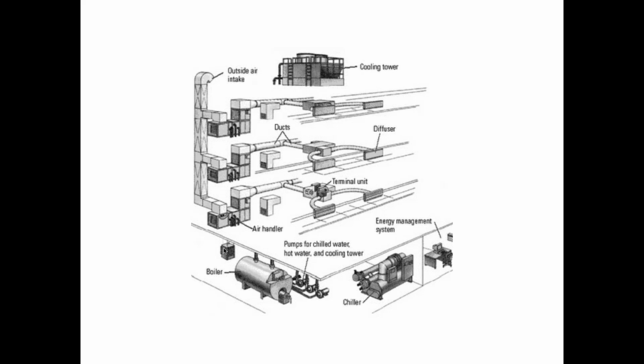So it's a problem. Instead of putting a Freon coil for cooling in each one of these air handlers, let's put a machine in the basement, which has an evaporative coil and a condensing coil in it, right? Except we're going to put those coils into big metal cylinders. So instead of blowing air over them, we run water through that cylinder over the coil. So what happens in the evaporative coil? It cools the water. So now we take that cold water, usually about 45 degrees, and we pump it throughout the building to each one of these air handlers. So now we're blowing the air over a coil called the chilled water coil.